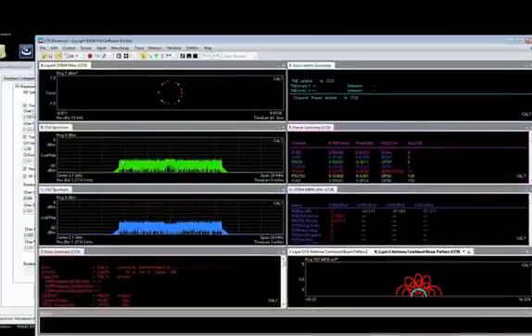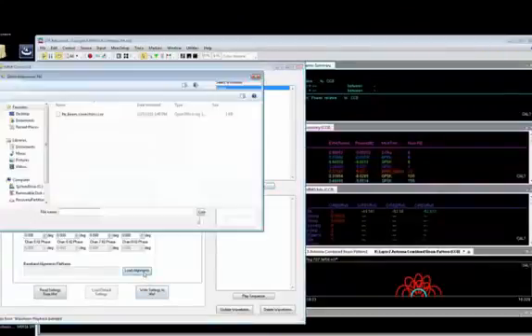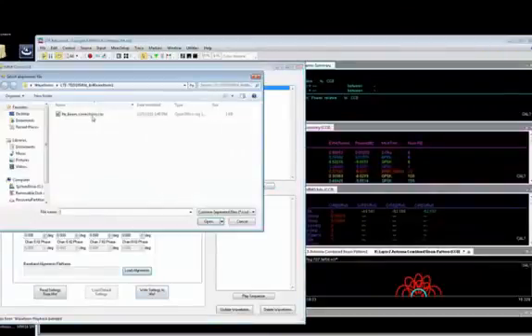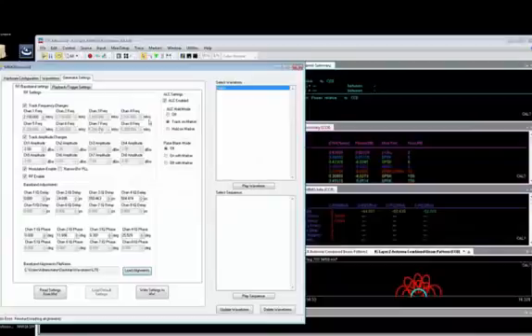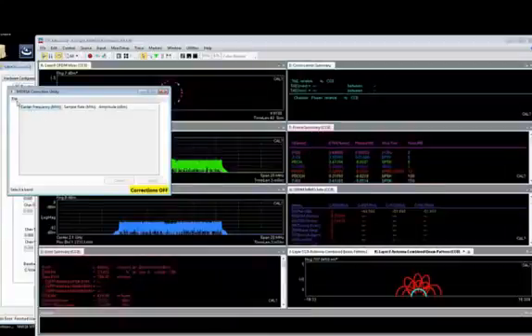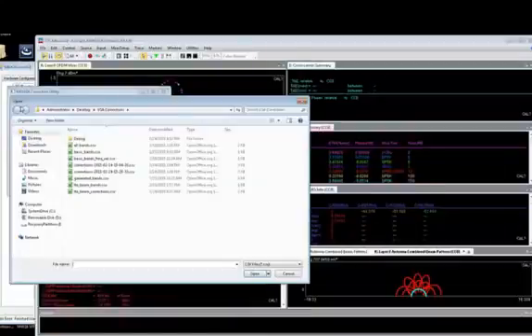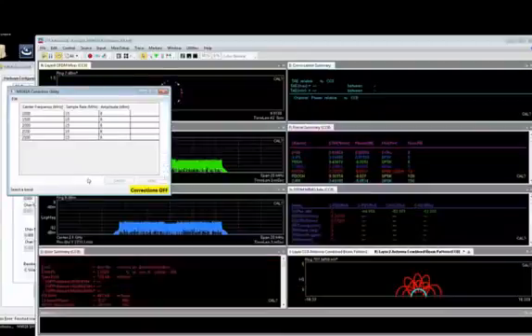To correct for time amplitude and phase differences between these channels, the Keysight correction utility with the reference solution provides an automated routine that captures baseband measurements at each of the defined frequencies and applies the corrections during the VSA measurements. We load the corrections from the previous calibration and apply.